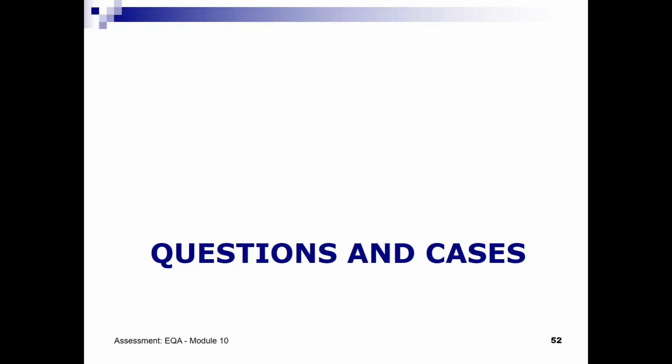Now, if you fail EQA and you do a root cause analysis and corrective action, when do you get assured that the corrective action is effective? Would it be the next EQA? Yes. You have QC and so forth, but ultimately you have to wait till the next EQA. Sometimes waiting till the next EQA takes too long. So one practice I would encourage everyone to do is, once you get your EQA and you've run it, freeze it, so you always have it to go back to.